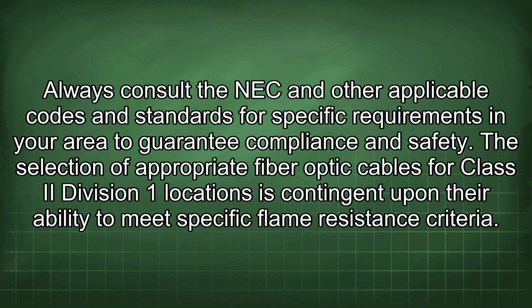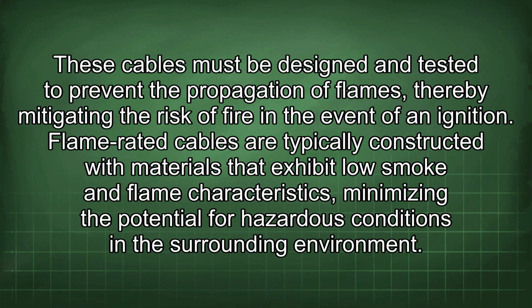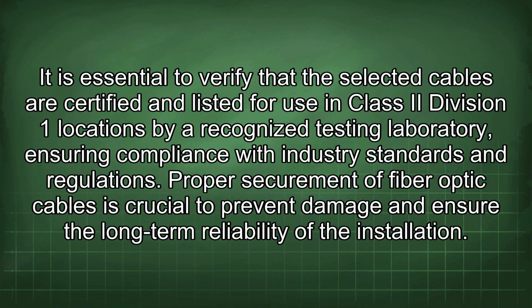The selection of appropriate fiber optic cables for Class II Division 1 locations is contingent upon their ability to meet specific flame resistance criteria. These cables must be designed and tested to prevent the propagation of flames, thereby mitigating the risk of fire in the event of an ignition. Flame-rated cables are typically constructed with materials that exhibit low smoke and flame characteristics, minimizing the potential for hazardous conditions in the surrounding environment. It is essential to verify that the selected cables are certified and listed for use in Class II Division 1 locations by a recognized testing laboratory, ensuring compliance with industry standards and regulations.